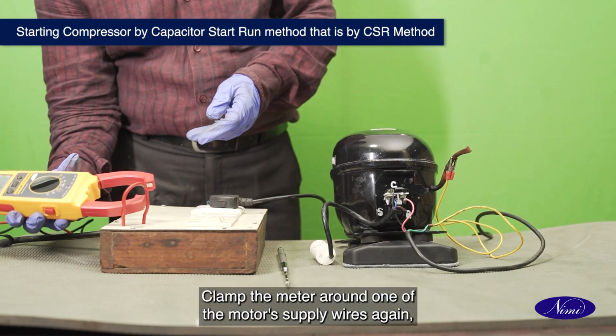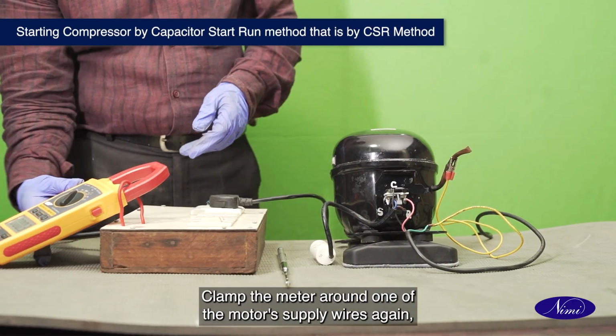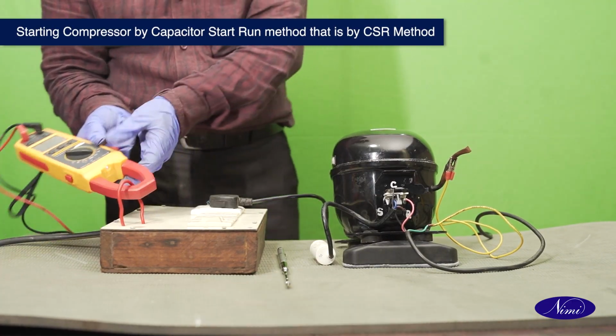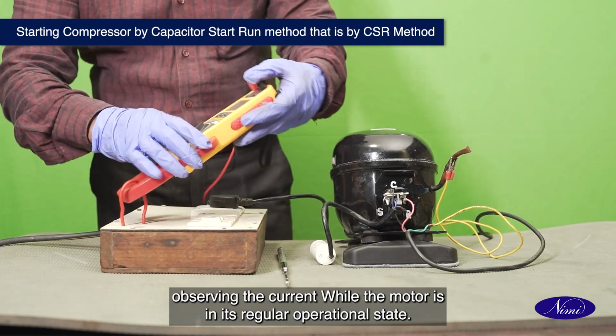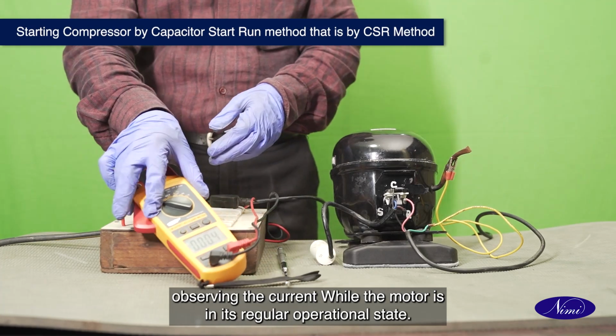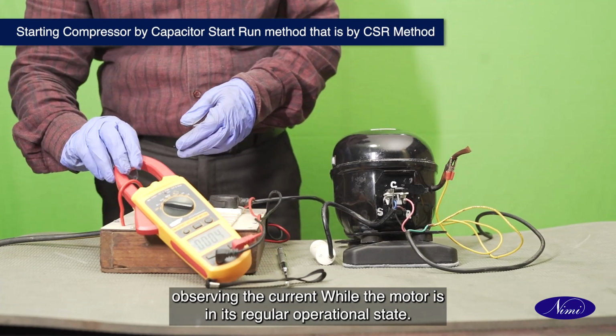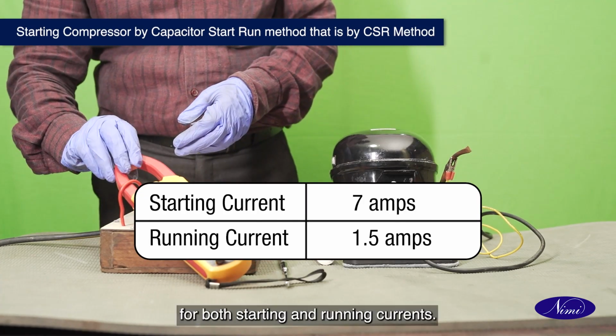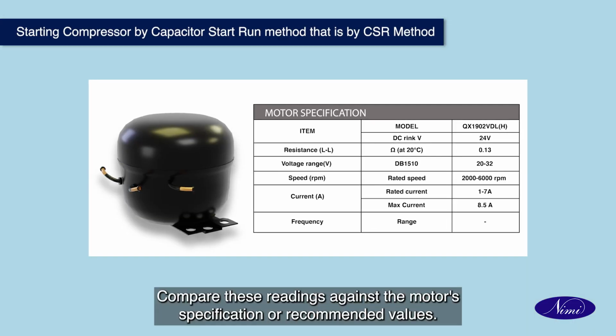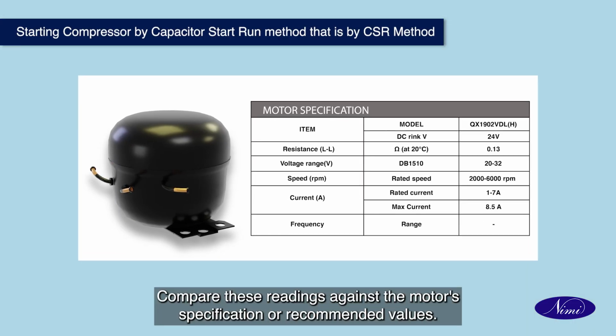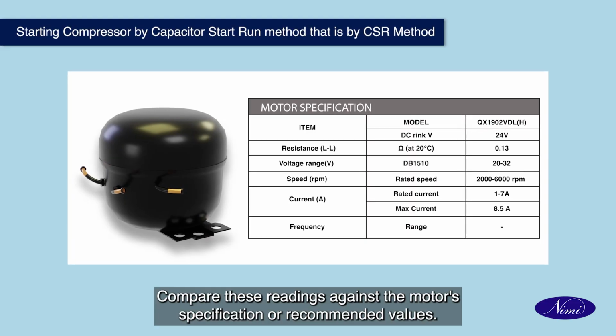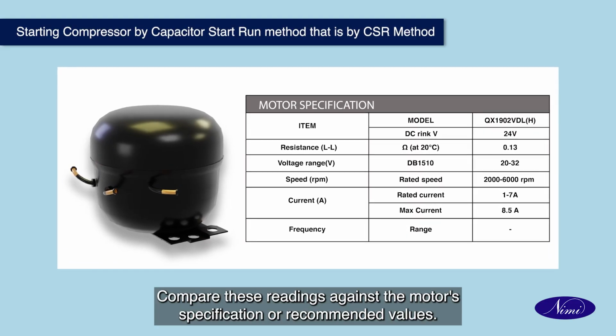Clamp the meter around one of the motor's supply wires again, observing the current while the motor is in its regular operational state. Note down the readings for both starting and running currents. Compare these readings against the motor's specification or recommended values.